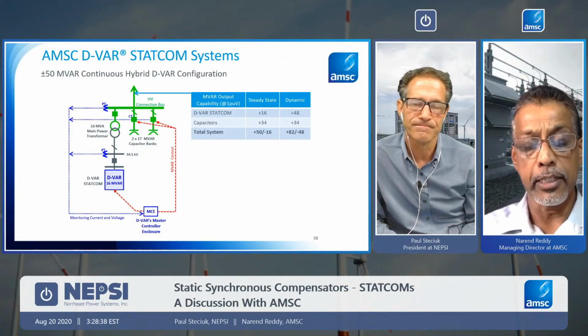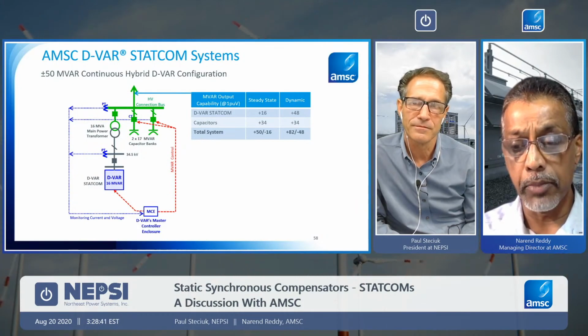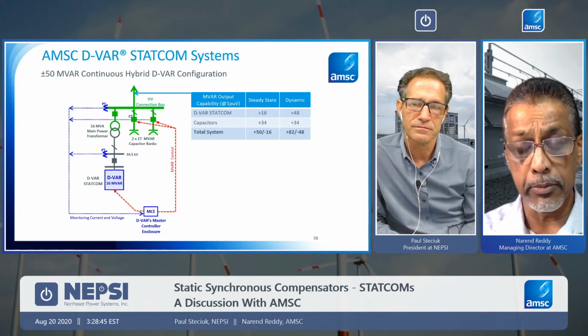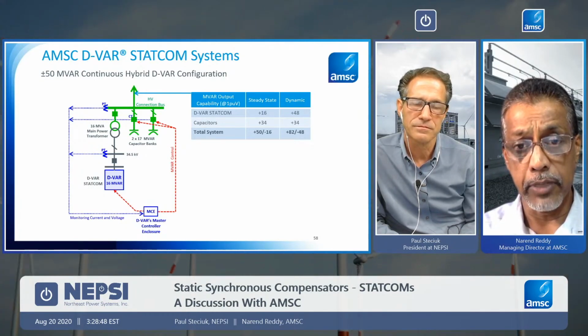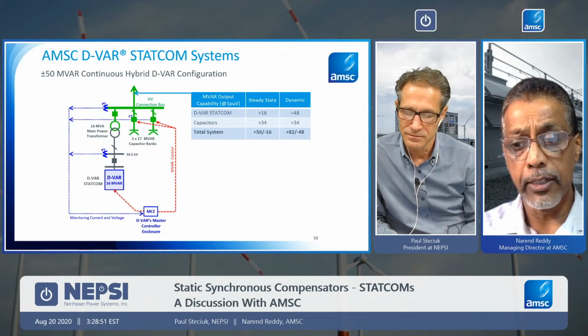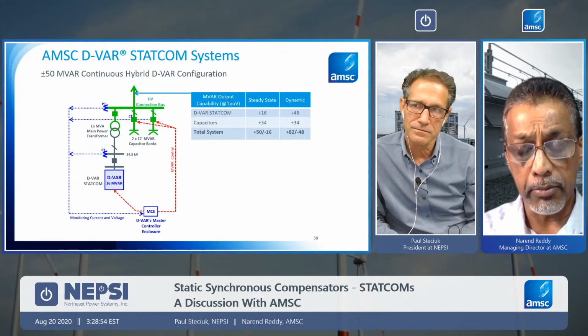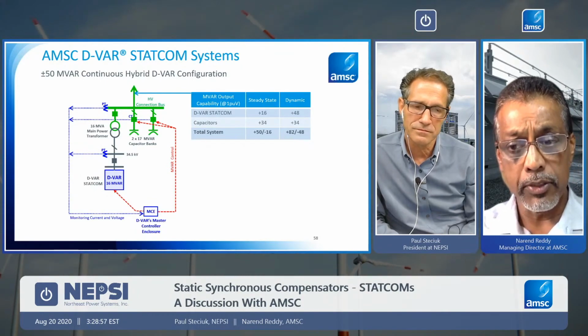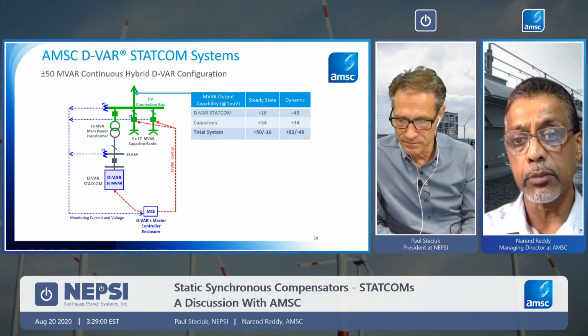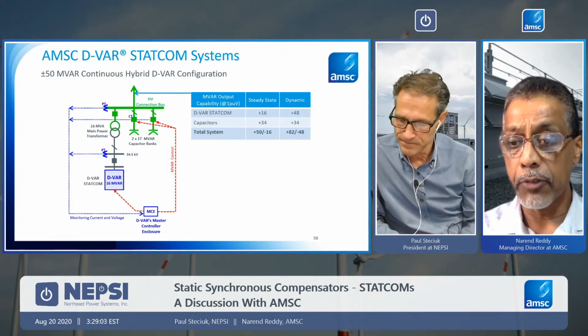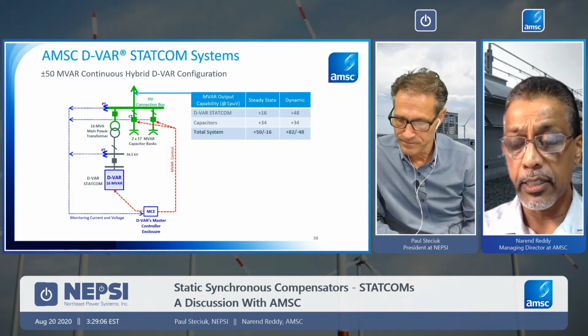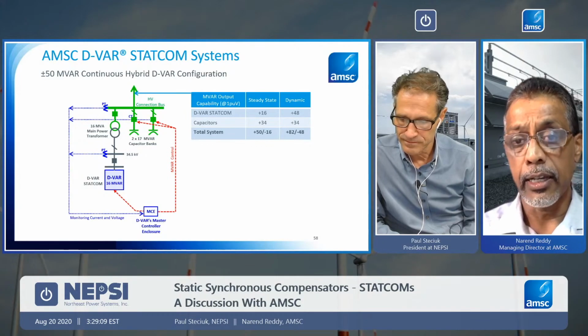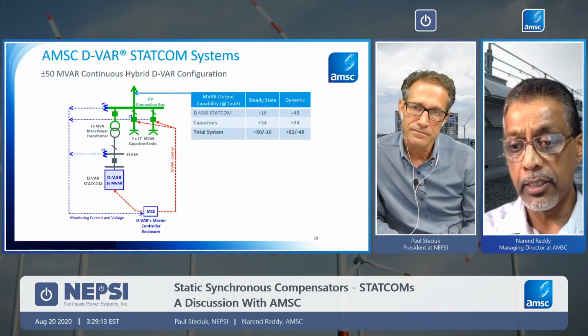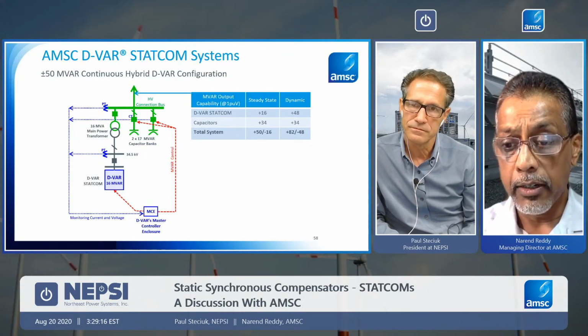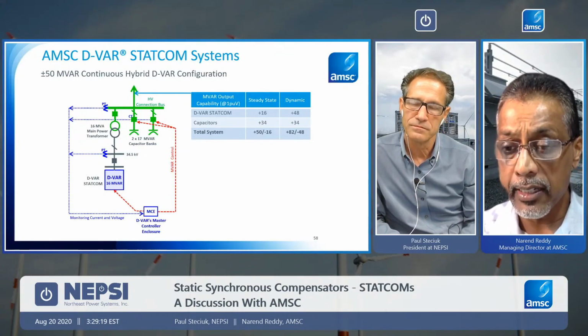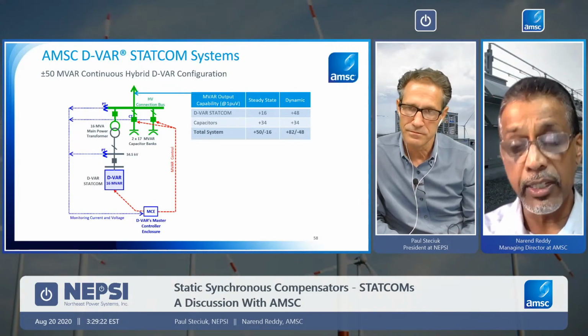Absolutely, and a hybrid solution is really the way that we've observed, and this is how we've actually presented to our customers, and it is very, very popular. It is the ability to fully define the characteristics of what the problem is, making sure that the dynamic portion of the solution overall meets the dynamic performance expectation of the system, but then for the longer term steady state requirements, we use the passive devices. For example, a 50 megavar. Let's say we do the analysis and it comes out that 50 megavar of dynamic compensation is needed, but not all of it is needed for long periods of time.